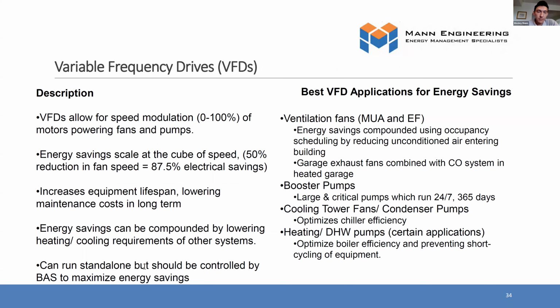So now variable frequency drives. I want to go over some of the best applications for variable frequency drives, because there are certain applications that make more sense than others. Now, as far as energy efficiency, obviously there's electrical savings. The energy consumption of a motor that controls a fan or a pump actually scales with the cube of the fan speed. So you get much more savings than you might think just by reducing the fan speed. But also the main savings comes from the downstream systems that the VFD is controlling.